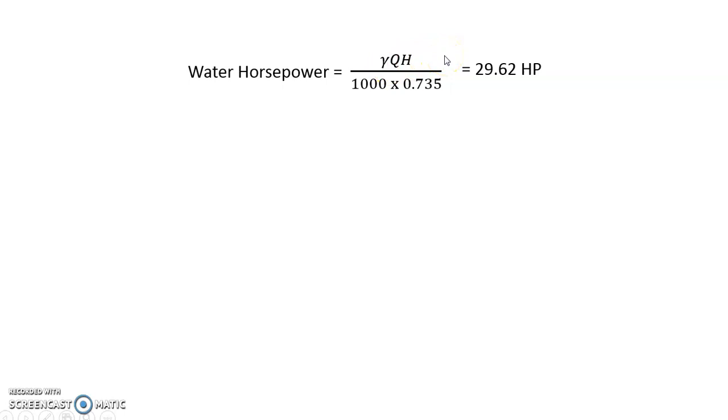Now horsepower of motor required or the brake horsepower is water horsepower divided by two efficiencies. In previous case we just had taken efficiency of a motor, but efficiency of pump is also given, so the modified formula is water horsepower divided by efficiency of motor as well as efficiency of the pump.